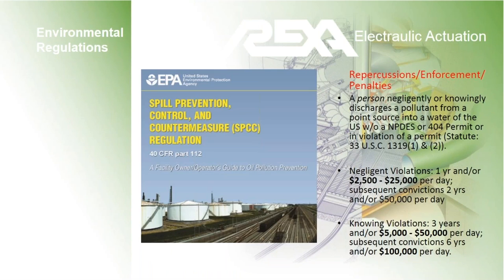How can environmental risk be reduced? What can the Rexa technology do to either reduce or eliminate a potential oil spill? There are unique advantages of using the Rexa. The closed-loop design can reduce oil volumes by as much as 95%, greatly cutting the risk of a spill. And with no requirement to maintain oil quality, there are no filters and conditioning systems that eliminate potential leak paths.